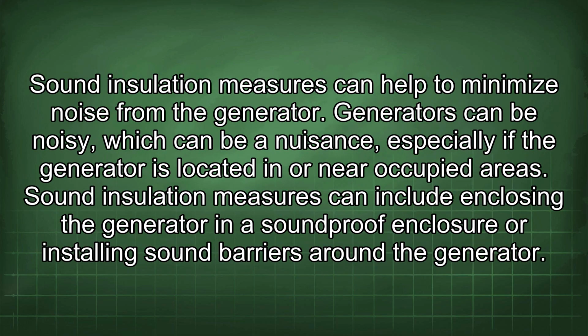Sound insulation measures can help to minimize noise from the generator. Generators can be noisy, which can be a nuisance, especially if the generator is located in or near occupied areas. Sound insulation measures can include enclosing the generator in a soundproof enclosure or installing sound barriers around the generator.